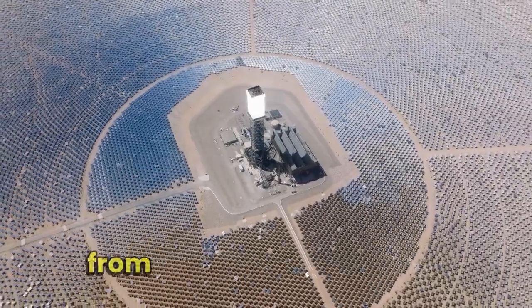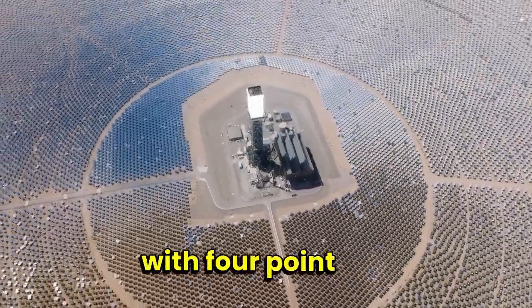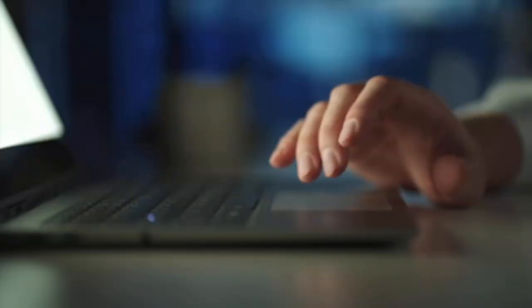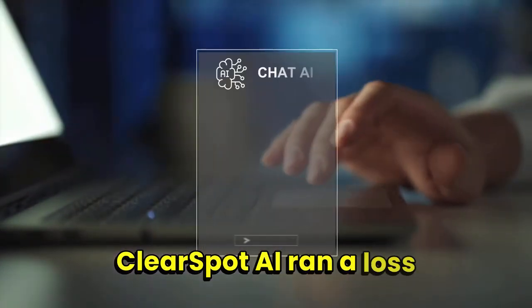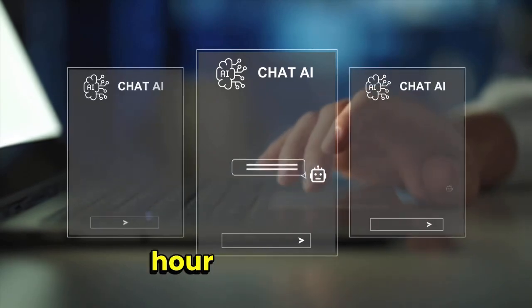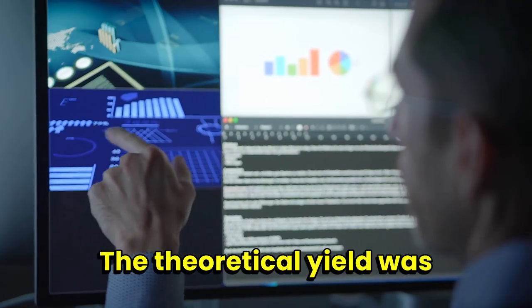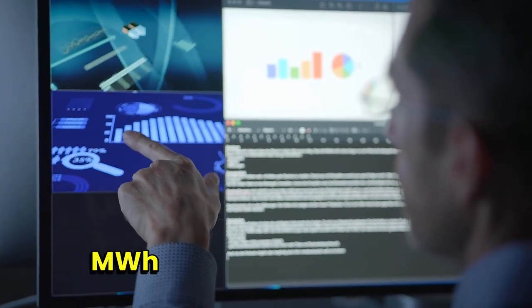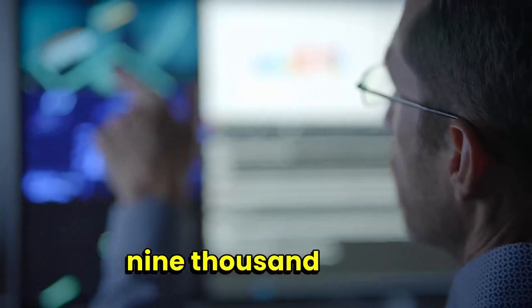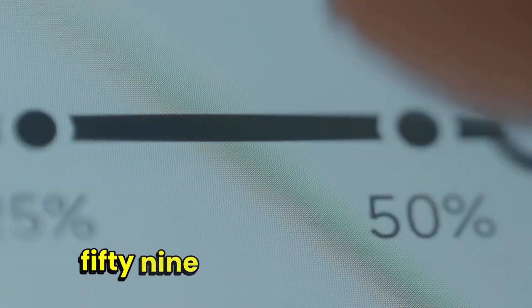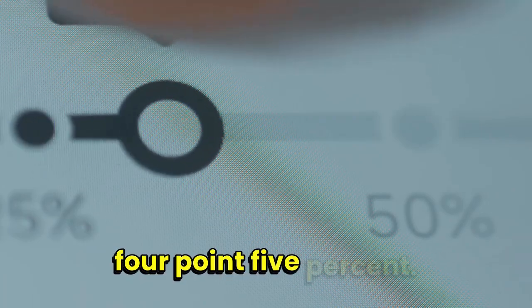Here is a real example from a 60 megawatt site with 4.5% underperformance. ClearSpot AI ran a loss waterfall analysis with a 48-hour turnaround. The theoretical yield was 10,200 MWh, and actual yield was 9,741 MWh. Loss was 459 MWh per month, or 4.5%.